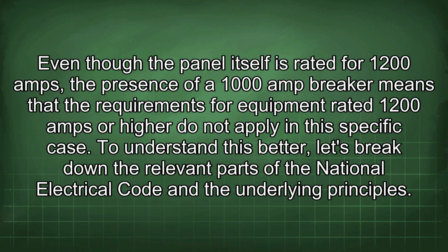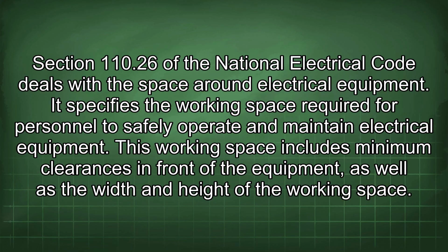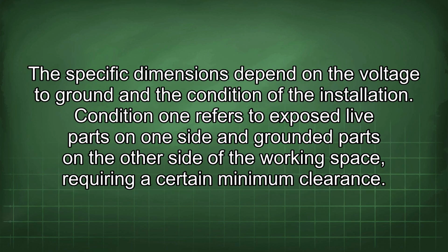To understand this better, let's break down the relevant parts of the National Electrical Code and the underlying principles. Section 110.26 of the National Electrical Code deals with the space around electrical equipment. It specifies the working space required for personnel to safely operate and maintain electrical equipment. This working space includes minimum clearances in front of the equipment, as well as the width and height of the working space. The specific dimensions depend on the voltage to ground and the condition of the installation.